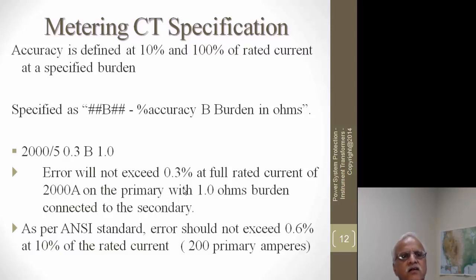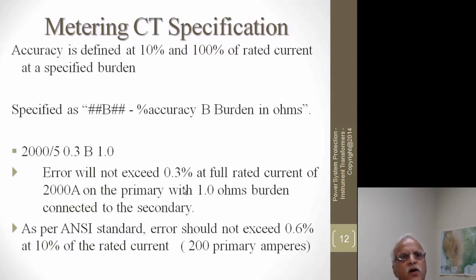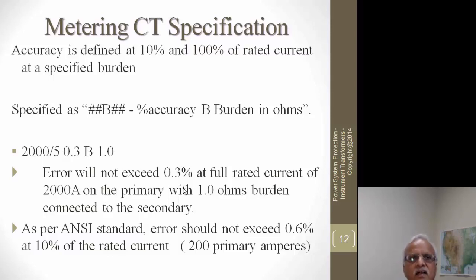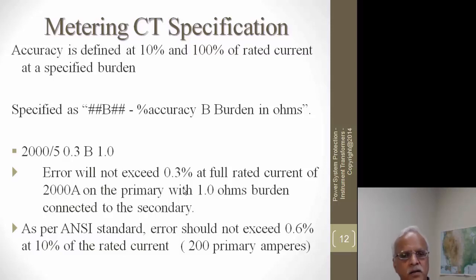Metering CT specifications are expressed as a number followed by the letter B and then another number — for example, 0.3B1.0. The '0.3' specifies the accuracy error: when the primary current is 2000 amperes and a one-ohm burden is connected, the accuracy error cannot exceed 0.3 percent. The ANSI standard also specifies that this error cannot be more than twice the specified value when the current is only 10 percent of rated — so at 200 amps, error cannot exceed 0.6 percent.